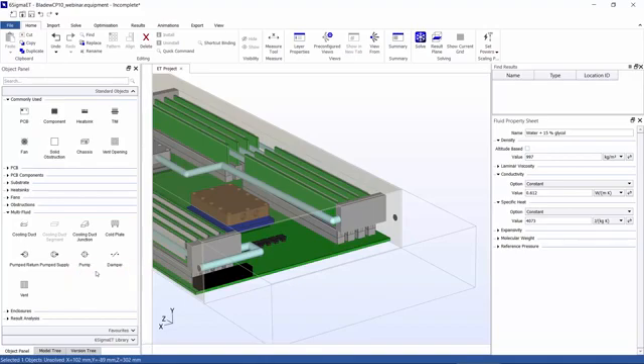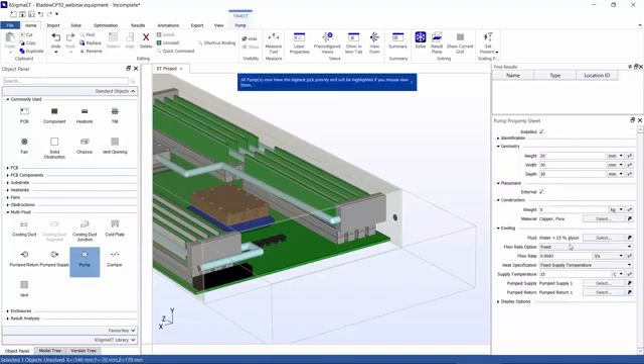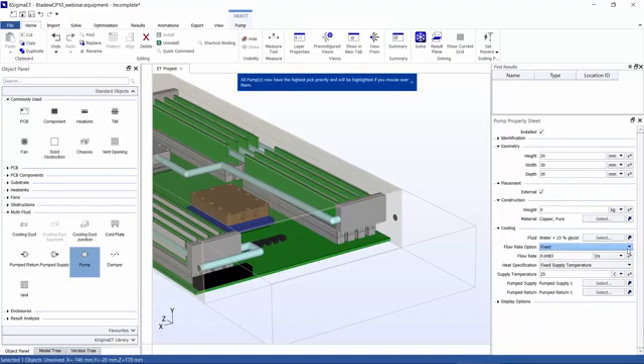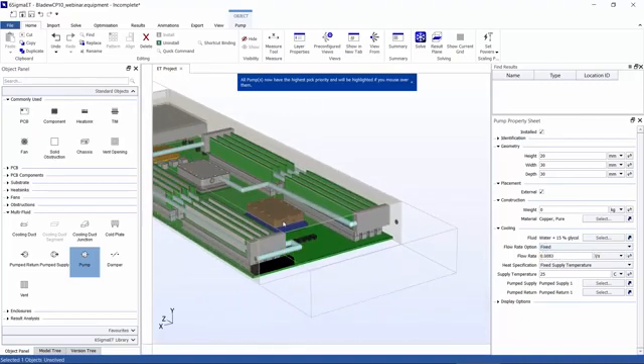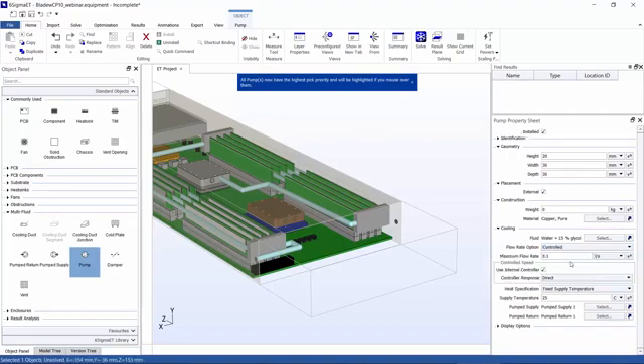If I go back to my pump, you can also see options for flow rate. We have a fixed supply which will provide a fixed volumetric flow rate, or we can use controlled flow rate. This will operate off of a sensor, typically controlling on a temperature. So, for example, you could have a sensor on these high-powered components, and if they reach above a certain temperature, it will change accordingly.